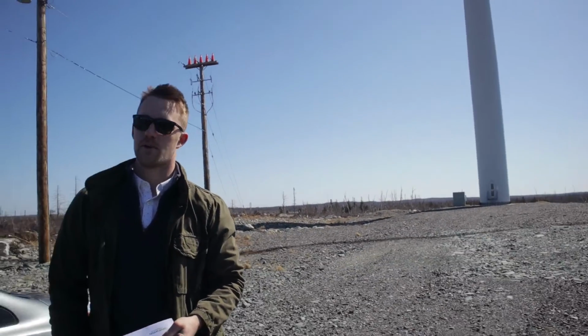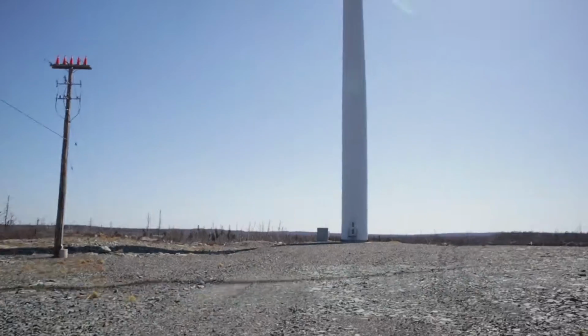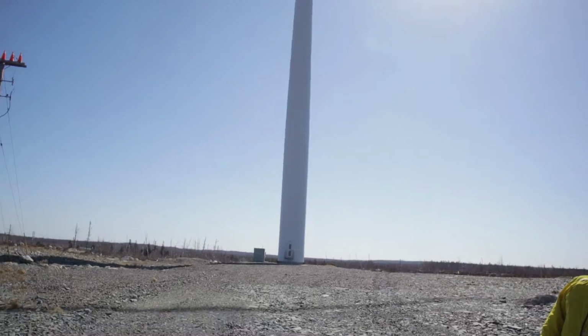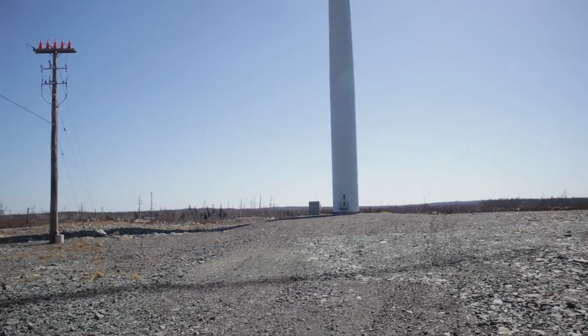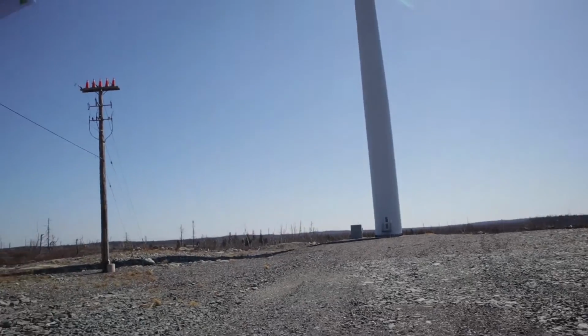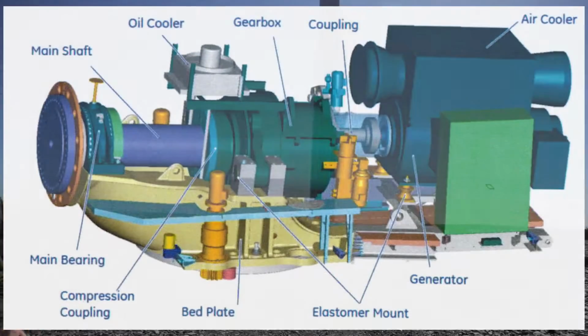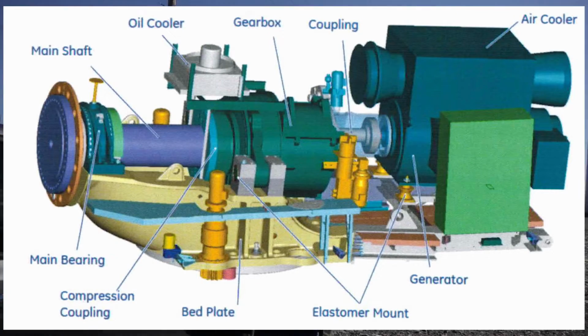They're pretty impressive. These nacelles are about 60 tons, and inside them the hub attaches to the main bearing, one big bearing, a low-speed shaft, and then a gearbox. The gearbox in this machine is a planetary followed by 2 helical stages. On bigger machines you'll see double planetaries.